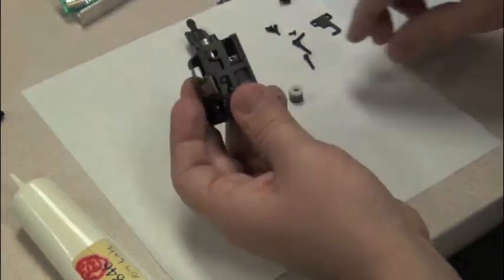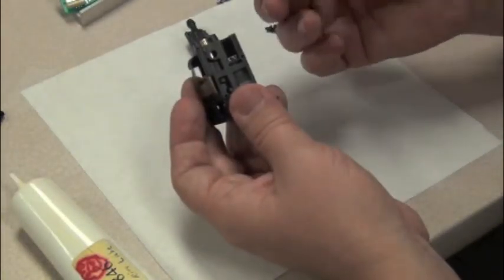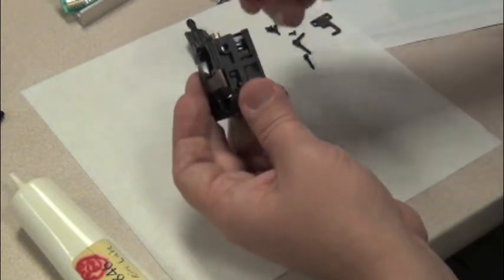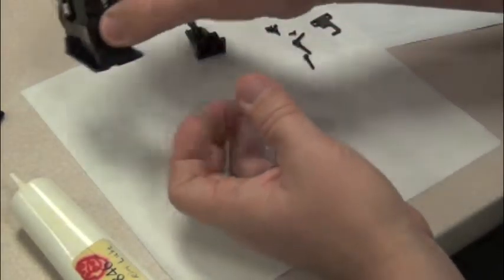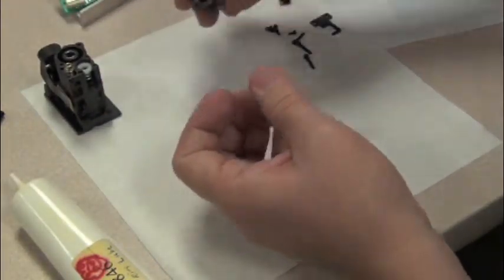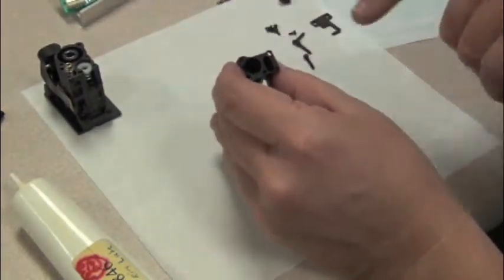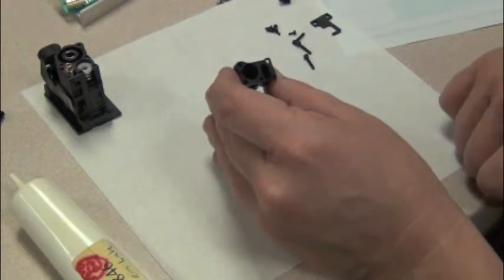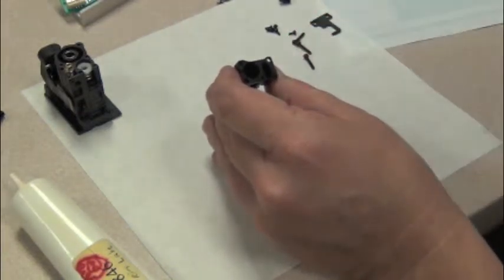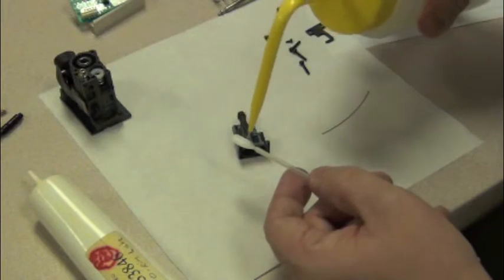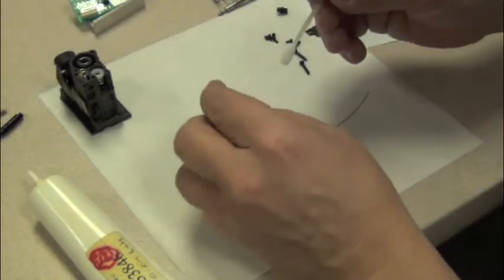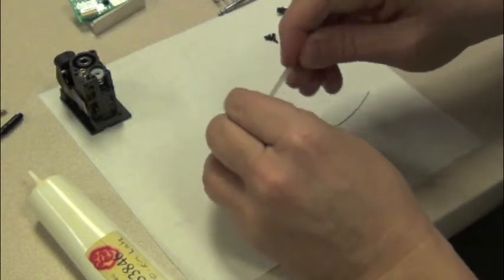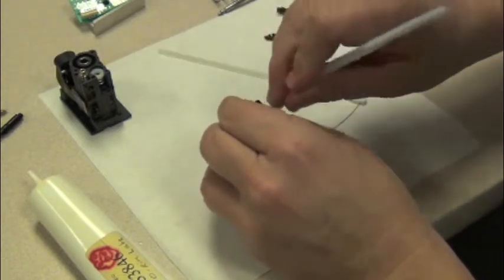Press down and seat the valve. Now take your valve preloader, white side up, and place it on top of the vacuum valve. Take the lower spindle assembly and put it on the side. Now let's grab the upper assembly and clean the upper housing. You should see a hole in the upper housing. Take the isopropyl alcohol, put on the ESD swab, inside the inner housing, clean that up. Pipe cleaner works well.